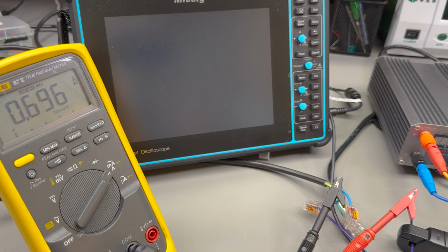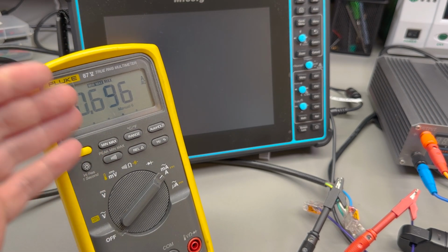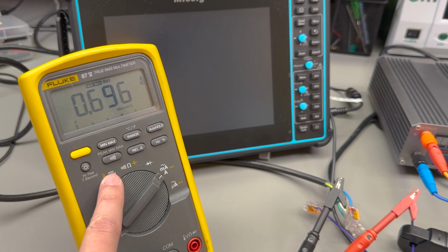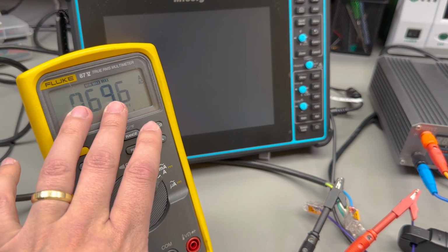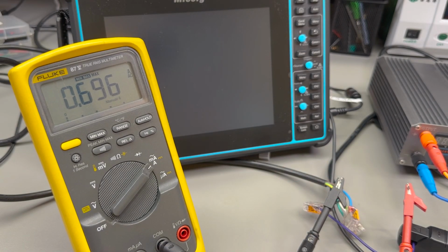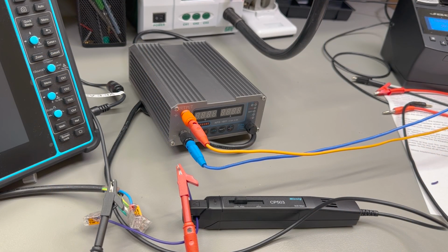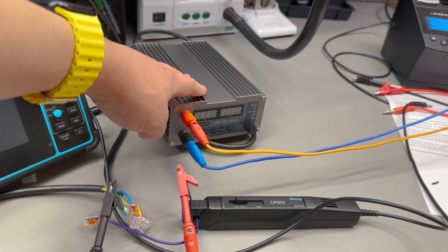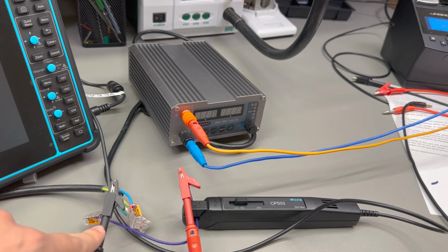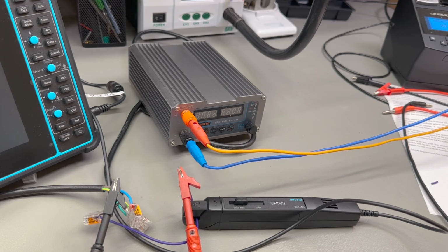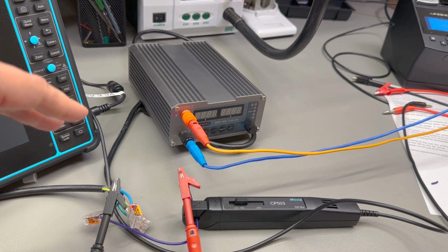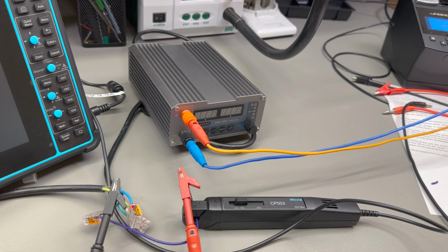Another useful measurement is where you might want to test inrush currents for some devices, and you might say, I have a min-max function on my multimeter, which can do that. Well, let me show you the difference between the min-max function on your multimeter, which has a very limited bandwidth, usually in the kilohertz range, and the current probe, which works in the tens of megahertz. The test setup is comprised of this switch mode power supply unit, which is feeding my electronic load, and we're doing the measurements on the AC line going to this power supply unit. When turning on the power supply, we should see an inrush current on the AC input, one that the multimeter should not be able to capture accurately.